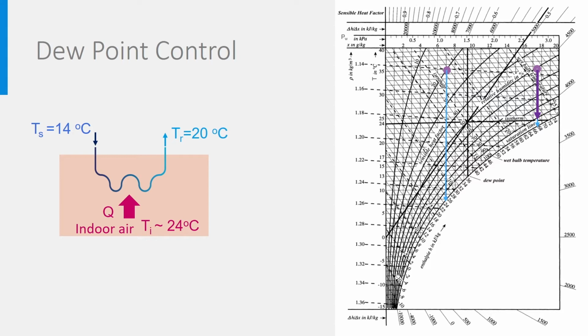If the cooling load Q is high, the supply temperature TS needs to be low. You remember that Q is m Cp delta T, so we may need a large delta T. Imagine that TS is 14 degrees Celsius.